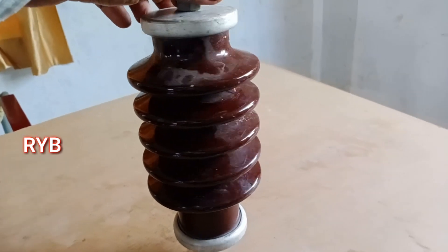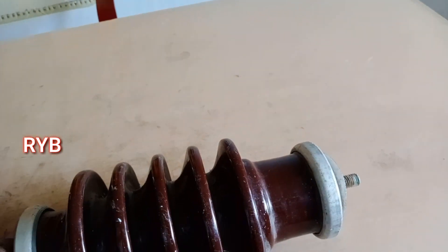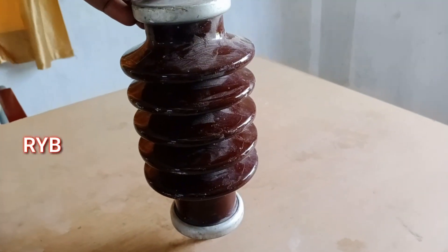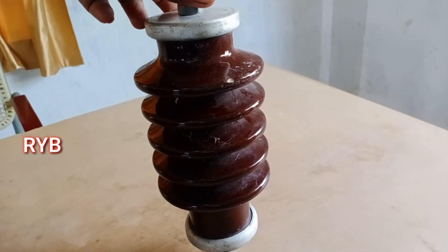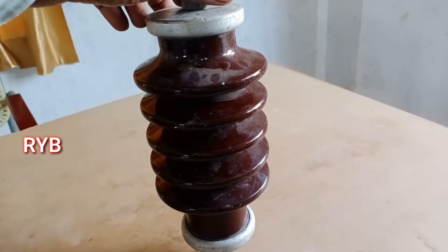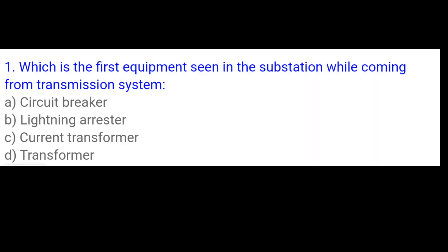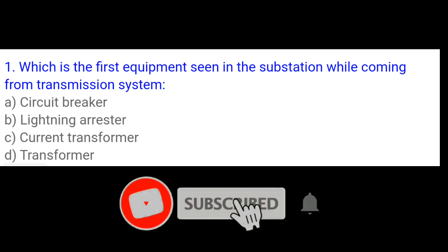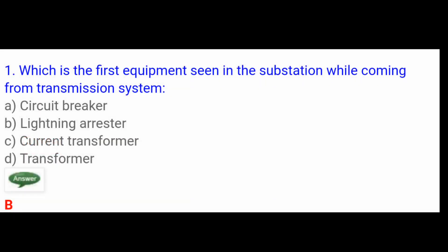Under normal voltage, the zinc oxide acts as a high resistance. Whenever lightning occurs, that voltage breaks the resistance of zinc oxide, and it acts as a lightning arrester, diverting the surge to ground. The lightning arrestor is the first equipment seen in the substation coming from the transmission system. This is the importance of the lightning arrestor. Please subscribe and press the bell icon to get more updates. Thank you.